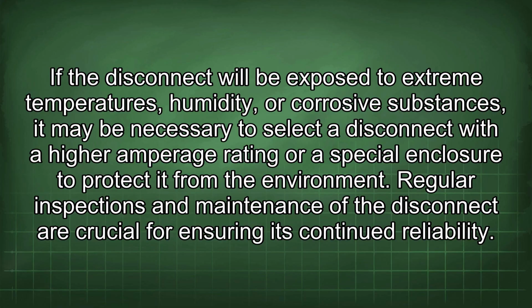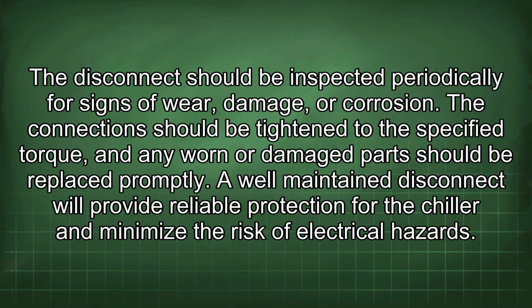Regular inspections and maintenance of the disconnect are crucial for ensuring its continued reliability. The disconnect should be inspected periodically for signs of wear, damage, or corrosion. The connection should be tightened to the specified torque, and any worn or damaged parts should be replaced promptly. A well-maintained disconnect will provide reliable protection for the chiller and minimize the risk of electrical hazards.